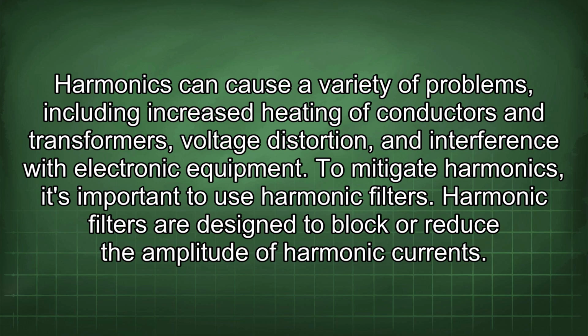Harmonics can cause a variety of problems, including increased heating of conductors and transformers, voltage distortion, and interference with electronic equipment. To mitigate harmonics, it's important to use harmonic filters. Harmonic filters are designed to block or reduce the amplitude of harmonic currents.